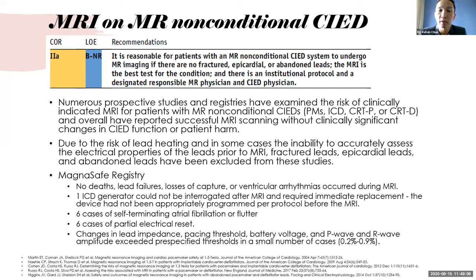The MagnaSafe registry is probably worth mentioning. It included MR non-conditional devices—I think there were 1,500 devices—that underwent clinically indicated non-thoracic MRI. Very importantly, there were no deaths, no lead failures, loss of capture, nor any ventricular arrhythmias that occurred during the MRI. Maybe one ICD could not be interrogated after the MRI and required immediate replacement, and it was mentioned that the device may not have been appropriately programmed per protocol before the MRI.